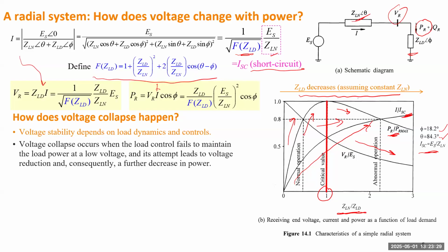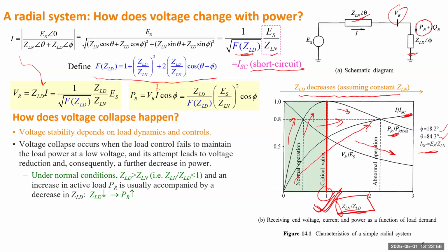The power further decreases. The controller believes it didn't increase much, so it keeps going, the power decreases further, and finally that's how voltage collapse happens. Okay, so to know when voltage collapse happens, you have to know where this line is, and to know where this line is, you have to know this ratio. This ratio involves both the load impedance, which you know from the load, and also the system, which is the line. But how can the load know what happened? So that's a short story on the cause of the voltage collapse.